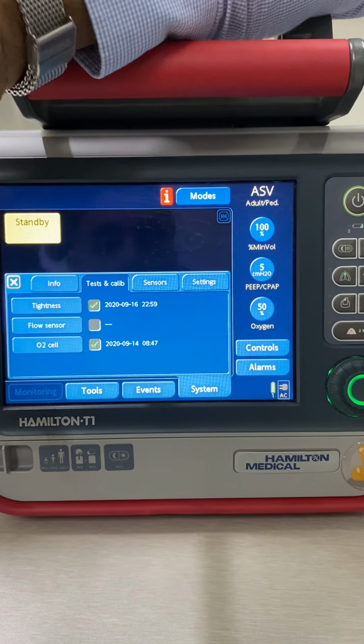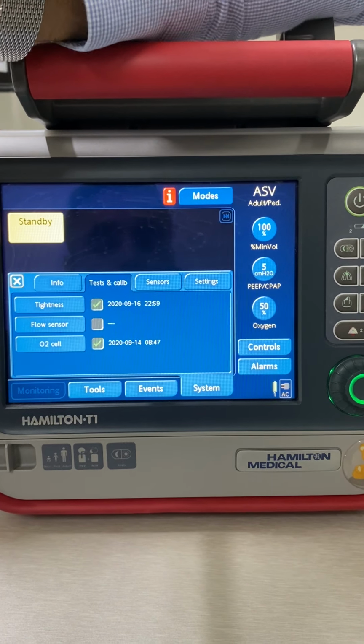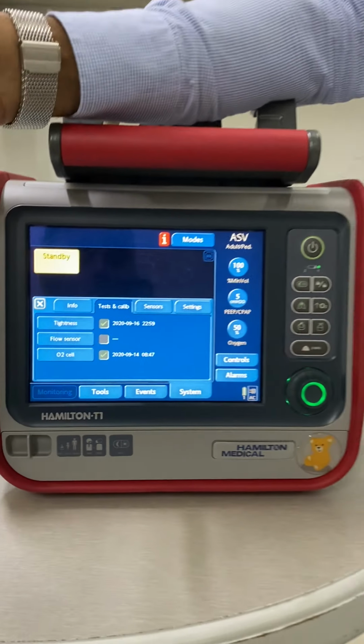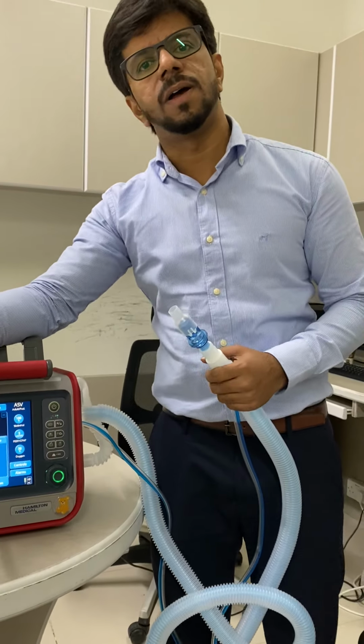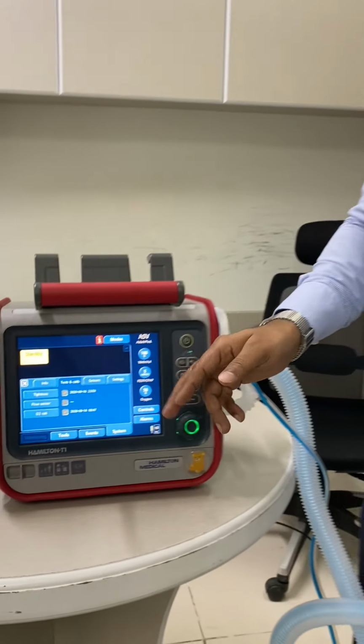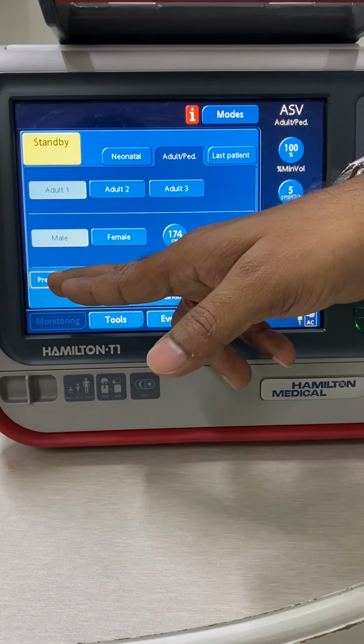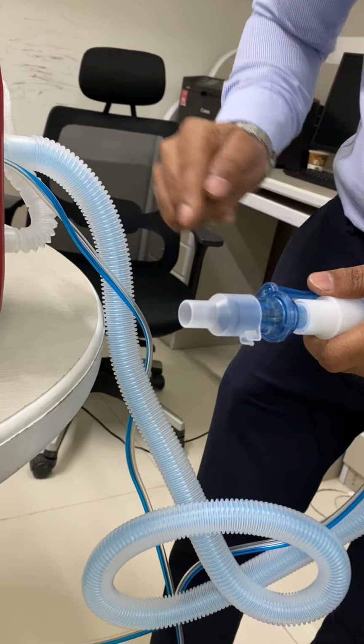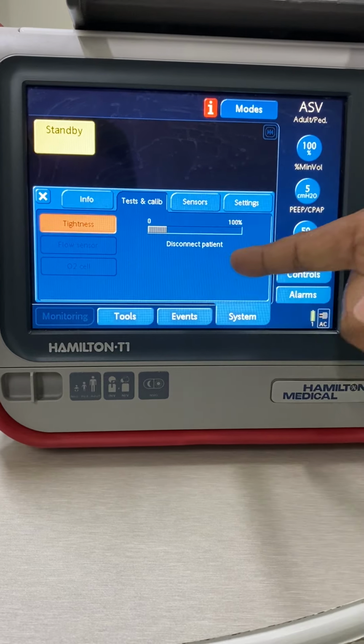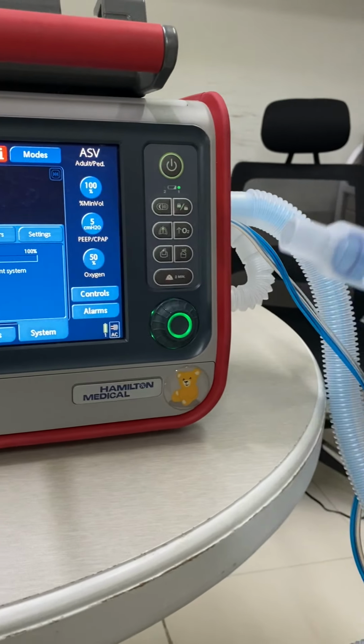But the O2 cell, you can calibrate whenever you get a message like "O2 cell calibration needed," or a low oxygen or high oxygen alarm. How to perform the tightness test? Go to the pre-op checkup. Make sure that you're not connected to any patient and the tubing system is open. Press the tightness test and it will give you the direction: disconnect the patient, no patient is connected.